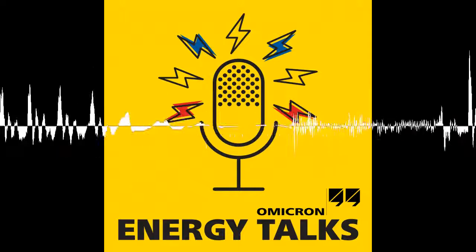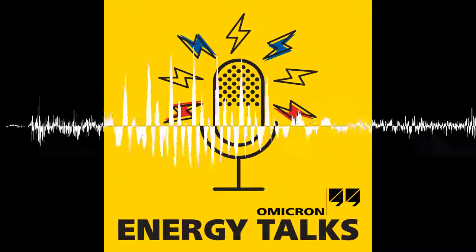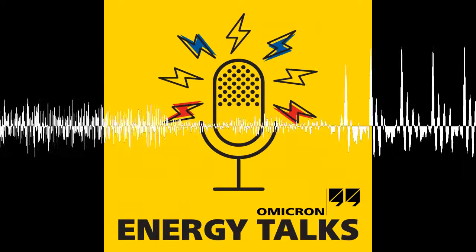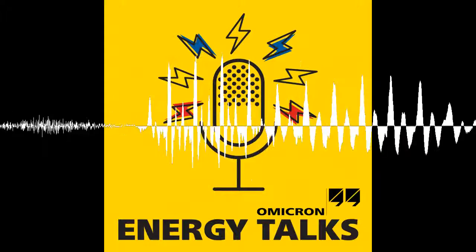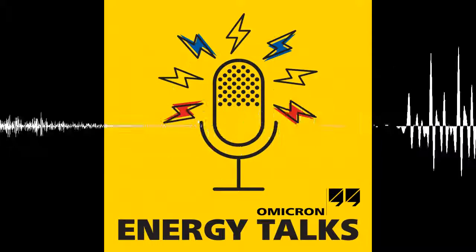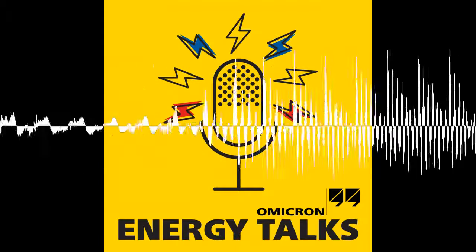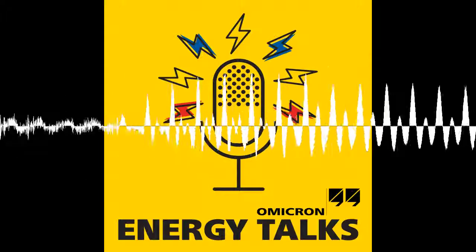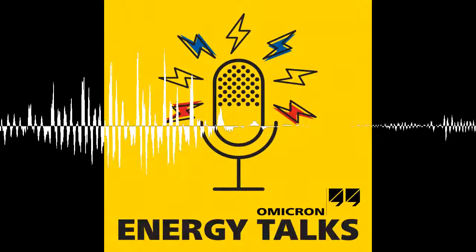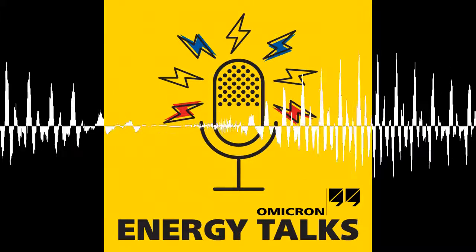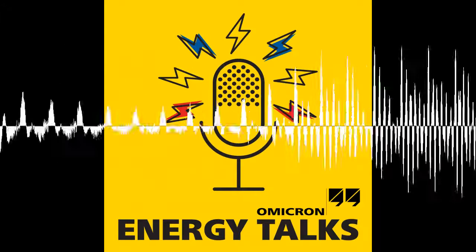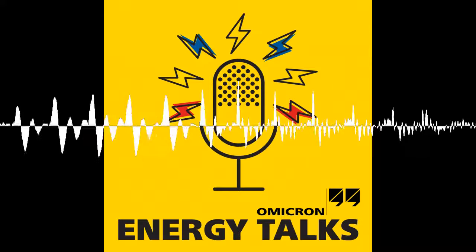Felix and Thomas, what is a capacitor voltage transformer and how does it differ from other instrument transformers? And what function does it have in a substation? Let me shortly explain it. A capacitor voltage transformer is one of the possible designs that we find at high voltage levels for voltage transformers. There are basically two options to design a voltage transformer: either a fully inductive design using more material, or a combination of a capacitive divider and a smaller medium voltage inductive transformer. The second kind of design is what we call the capacitor voltage transformer.